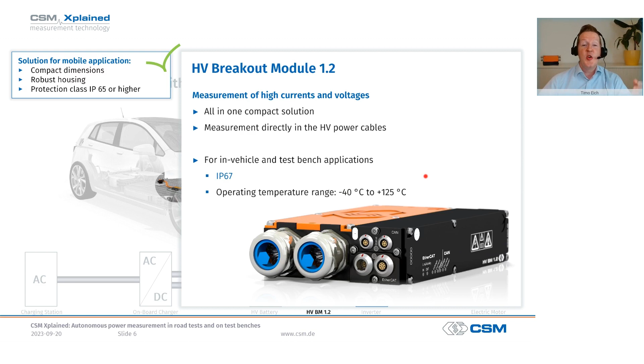Now, what's very important, the current measurement is conducted with a fully temperature compensated shunt module, and it is possible to measure inner conductor currents up to plus minus 2000 amps. Voltages can be measured up to plus minus 2000 volts, and the data acquisition is performed with a sampling rate of 1 million measuring points per second and per channel. That's 1 megahertz sampling rate.